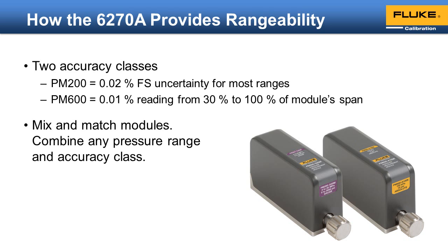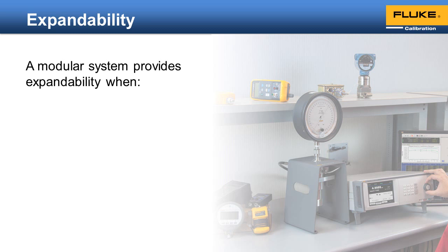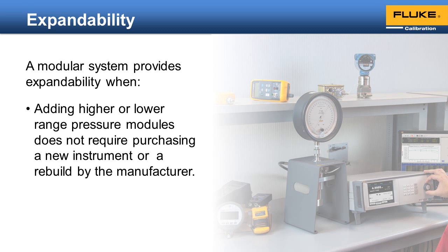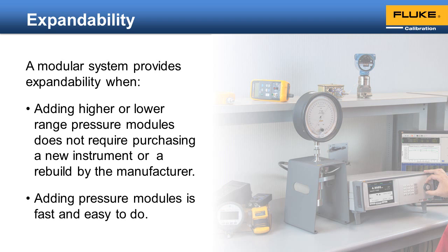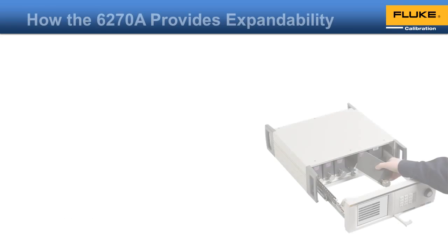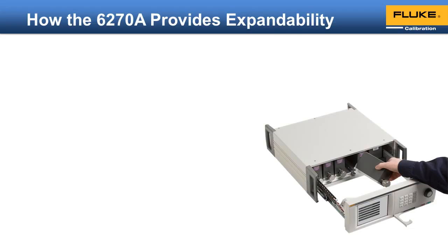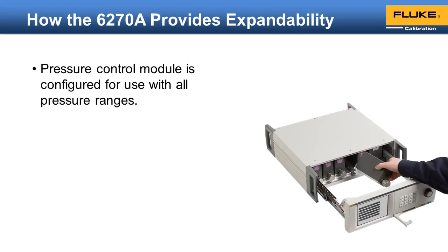Combine any pressure range and class so you can meet your needs exactly. Your calibration needs change over time. With a traditional non-modular pressure controller calibrator, it is next to impossible to change the range or accuracy class. With a properly designed modular system, the pressure controller calibrator can grow with your needs. To provide expandability, you should be able to add higher or lower range pressure modules without purchasing an entirely new instrument or sending the unit back to the manufacturer for upgrade. And you should be able to add these pressure modules quickly and easily. The 6270A meets these requirements. The pressure control module is configured for use with all pressure ranges.